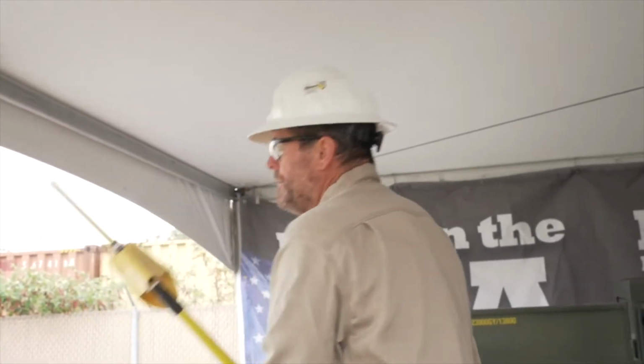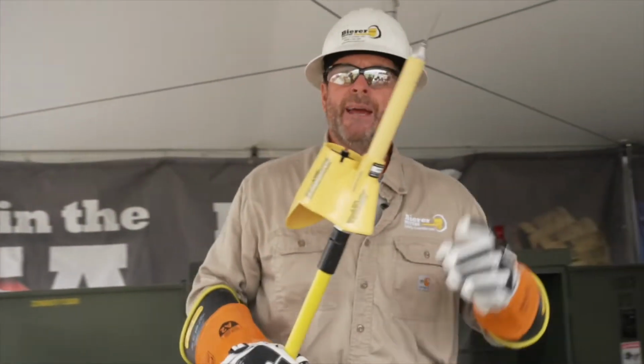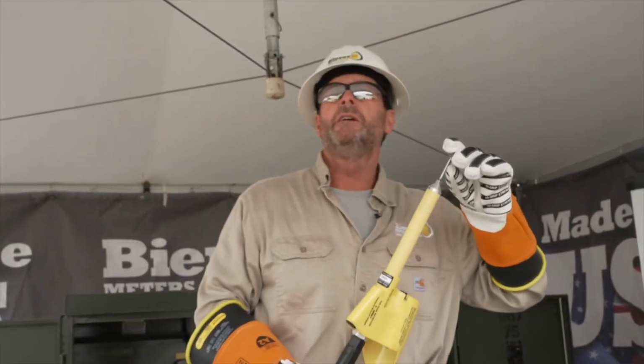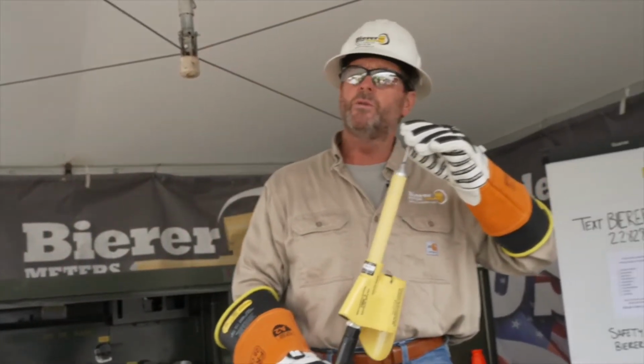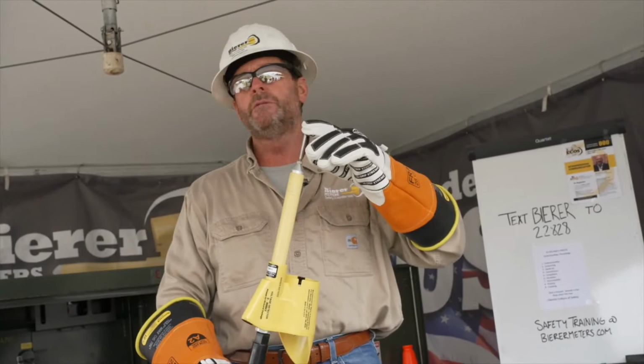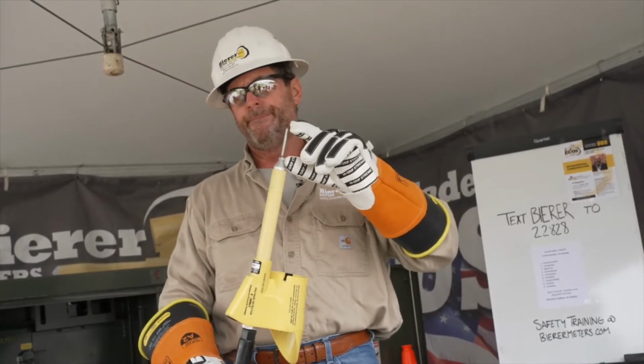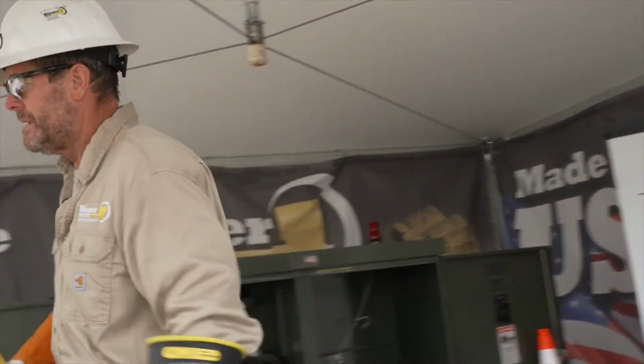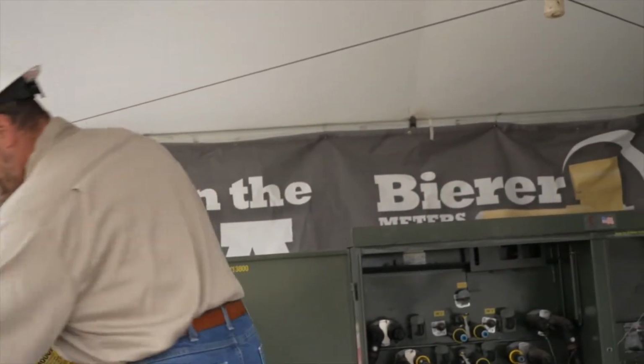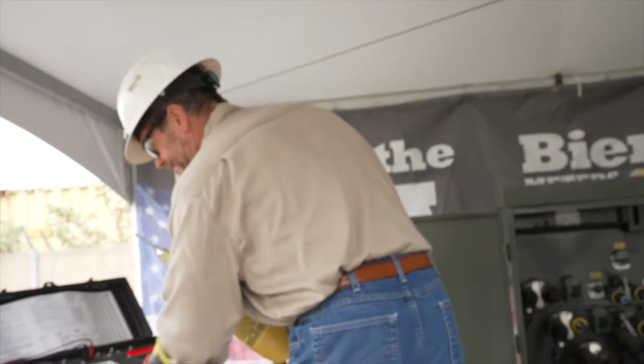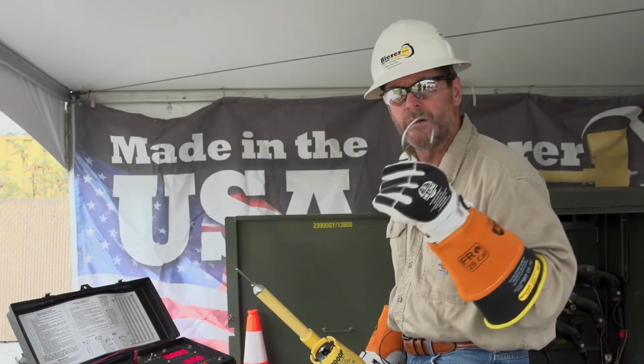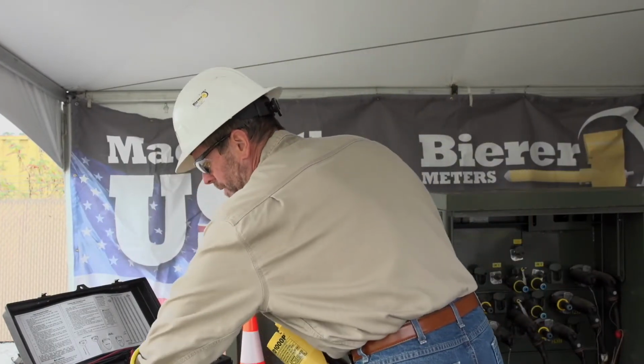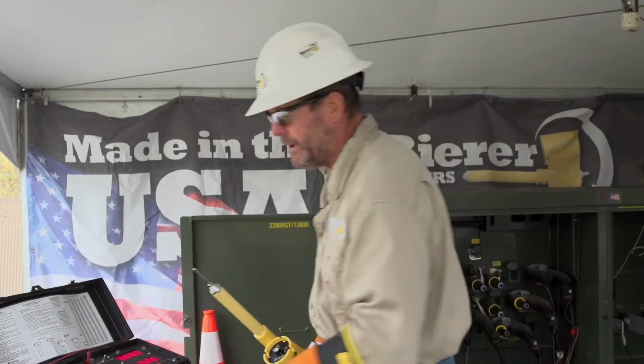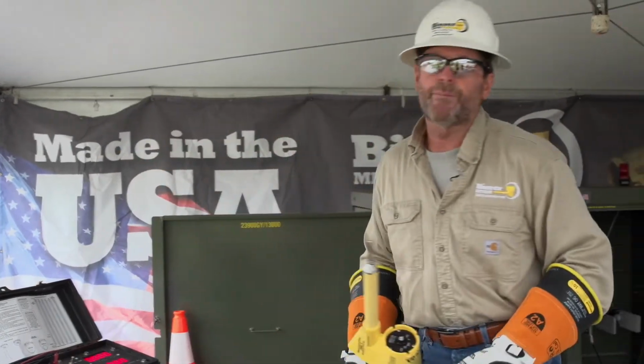We're going to use our tools, and you're going to be using your hot sticks. Make sure that when you're using a device, phasing tool, voltage indicator, you're always going to use the proper accessory on that cone tip. You got a straight probe, bushing adapter, a hook probe, maybe an elbow adapter going into the elbow. Always use the proper accessory.